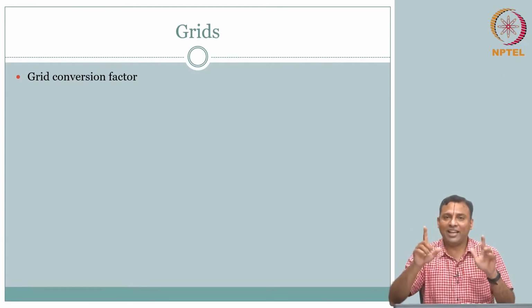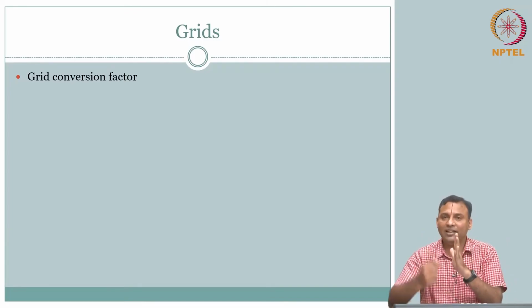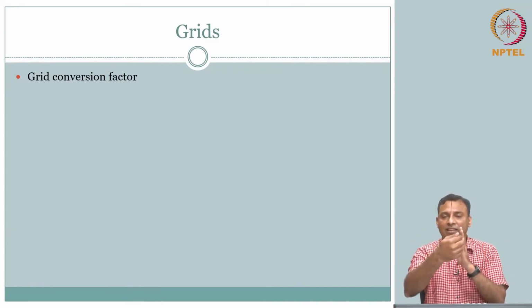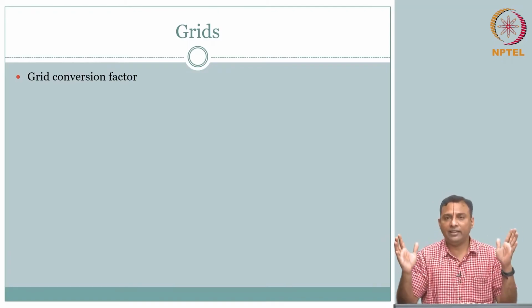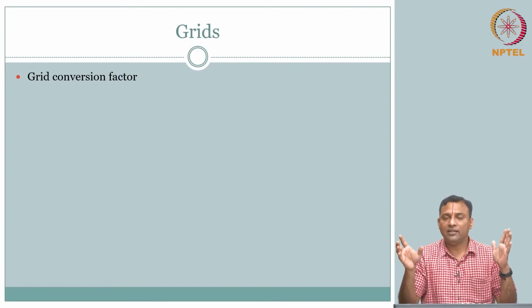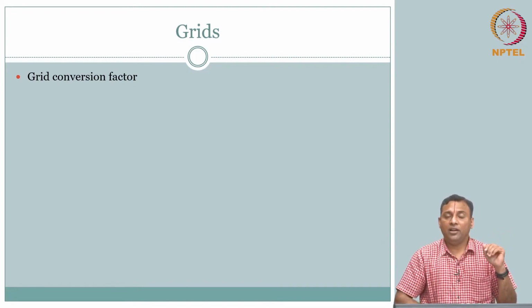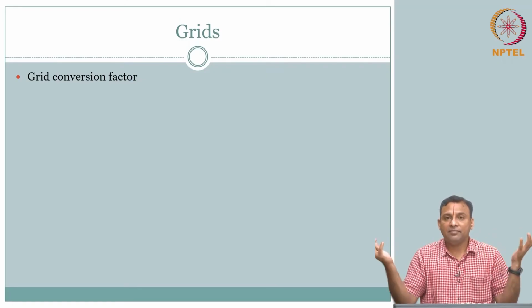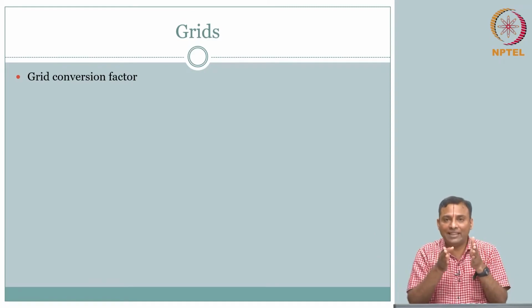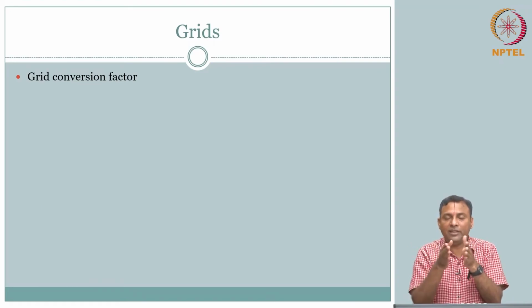Whatever is coming at the angle I have reduced. But what happens when the signal, the photon, comes and hits the lead? There is a grid of leads, or attenuating material. What happens when the photon is actually hitting that? Well, if it is hitting that, that is also lost. So, in some sense you are getting the signal only through the transparent window that is sandwiched between the gap between the leads.